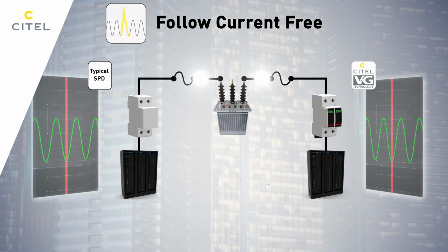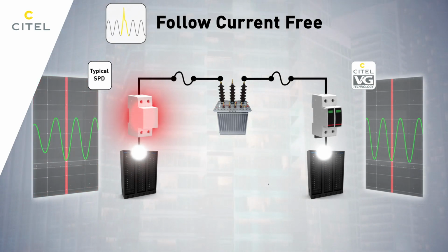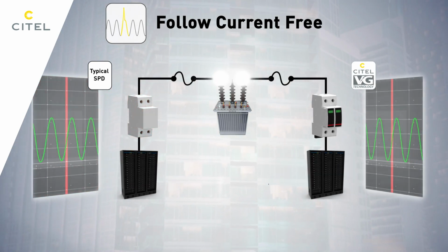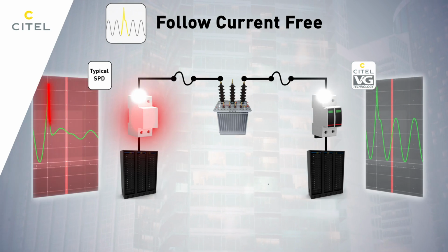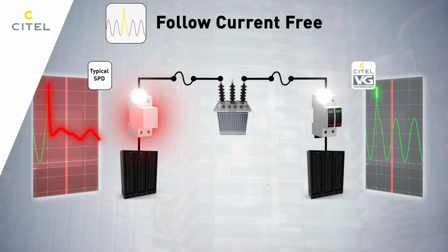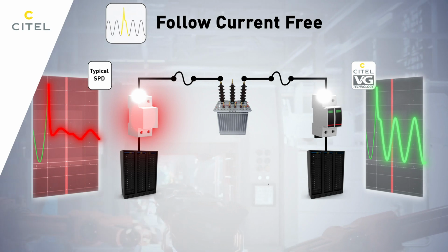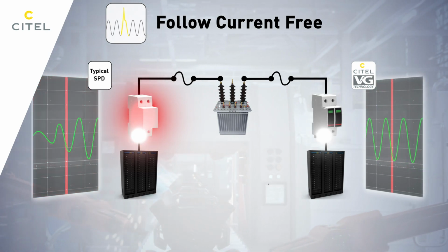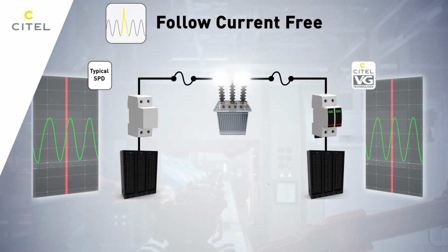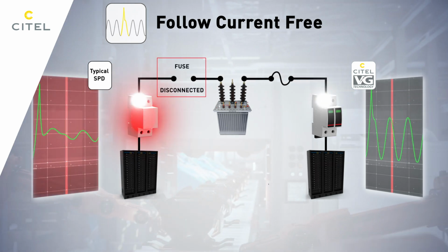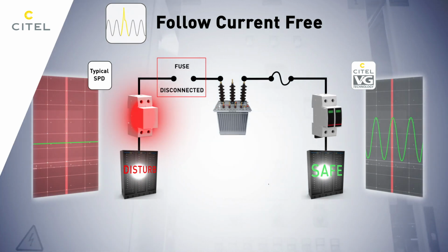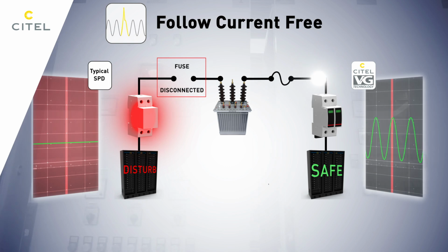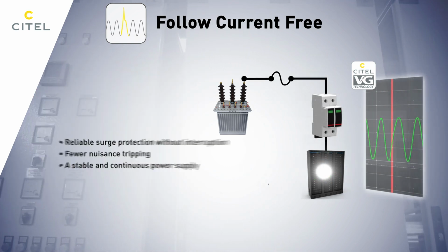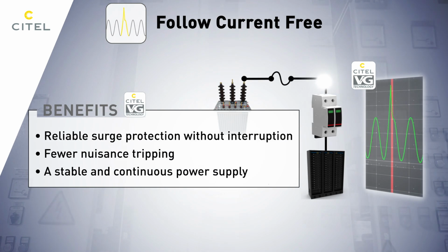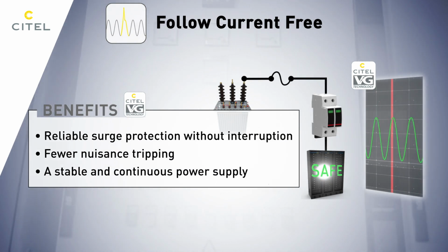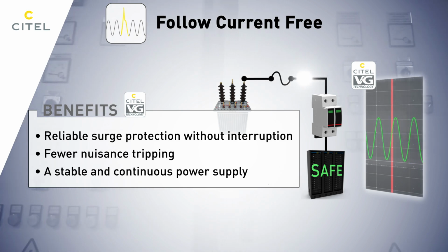When a conventional surge protection device activates, it can generate a follow current, an unwanted current that continues to flow through the power network after a surge event. This current can cause unnecessary tripping of circuit breakers, disrupt system operation, and reduce overall protection efficiency. With VG technology, this phenomenon is completely eliminated. The SPD instantly returns to a high ohmic state without causing a short circuit, and the protection device does not trigger an unnecessary disconnection. Immediate benefits: reliable surge protection without interruption, fewer nuisance trippings, a stable and continuous power supply.